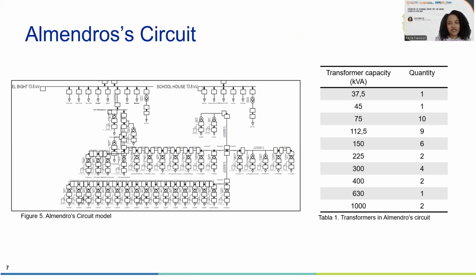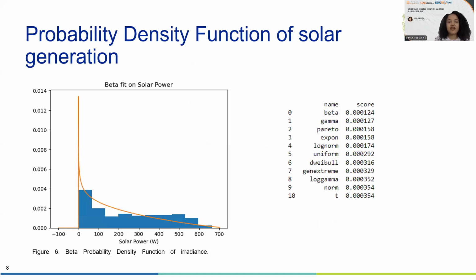This is the model of the Almendros circuits in DigSilent. It has a total load of 2.77 megawatts. Probability density function of solar generation is used to integrate the uncertainty of these kind of sources into the simulations, and it was calculated from the irradiance data measured by the Instituto de Hidrología, Meteorología y Estudios Ambientales, IDEAM, at the airport of San Andres, and finding that it matches a beta probability.